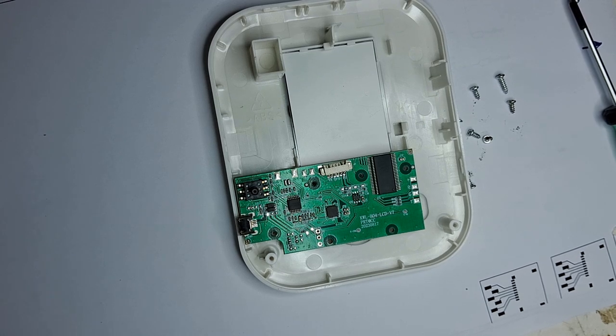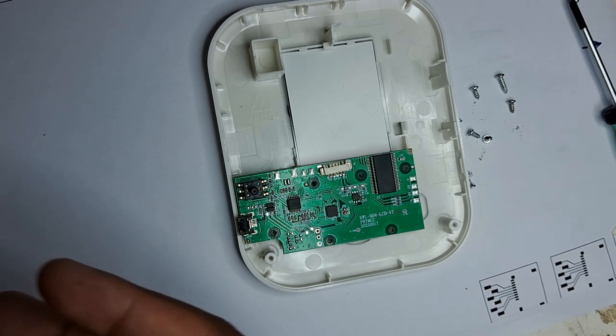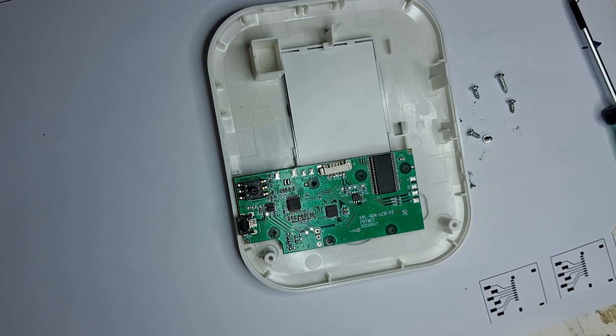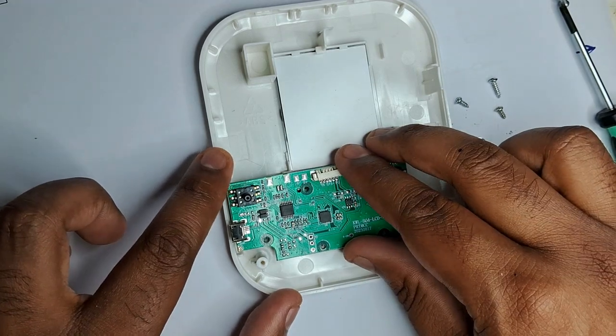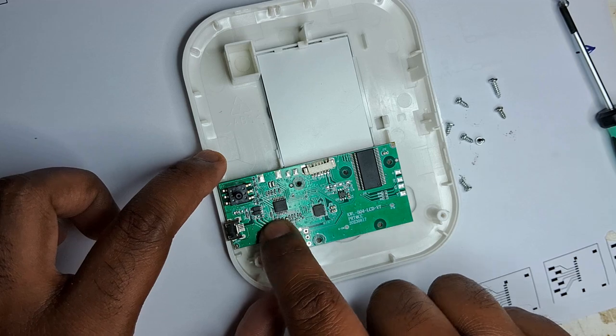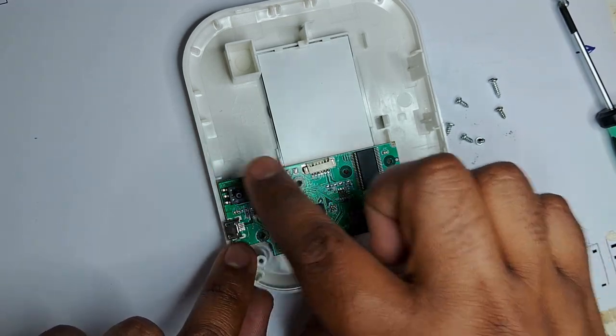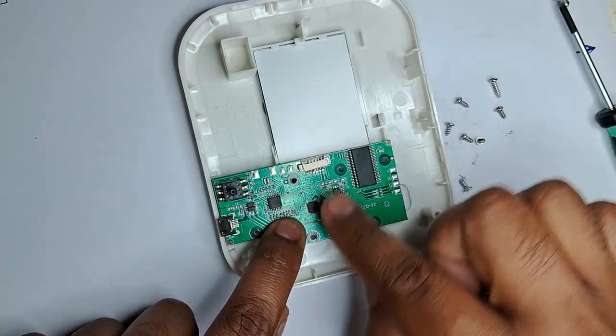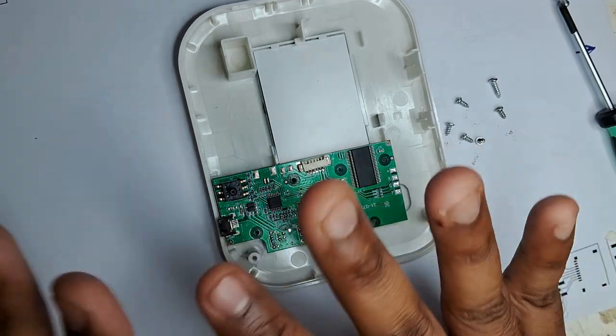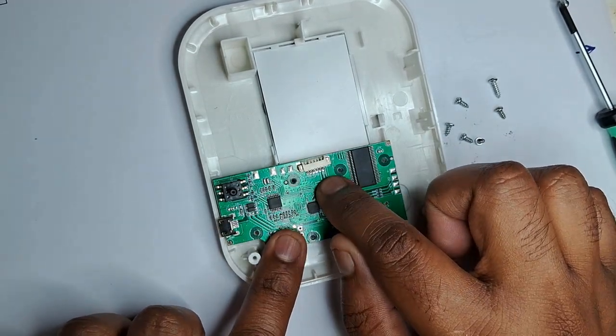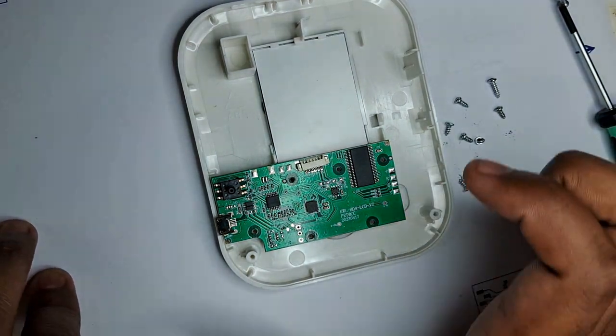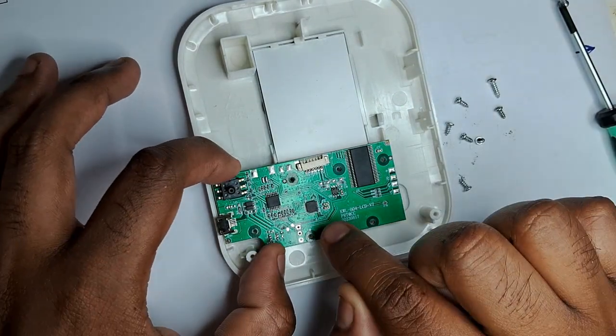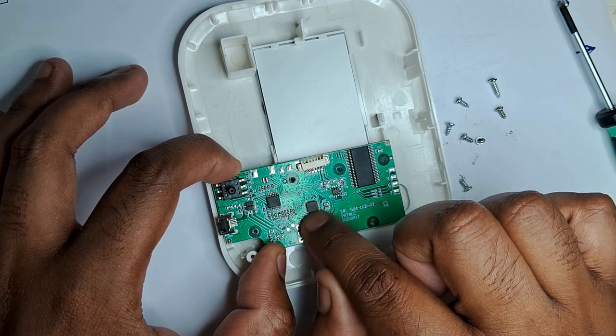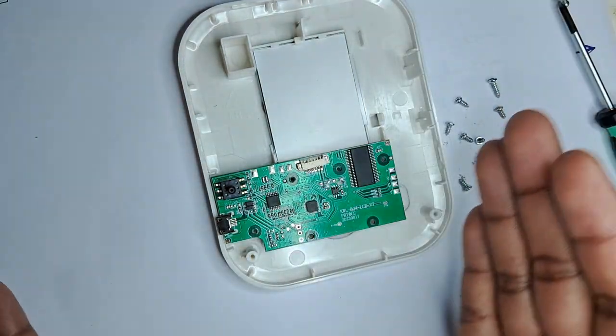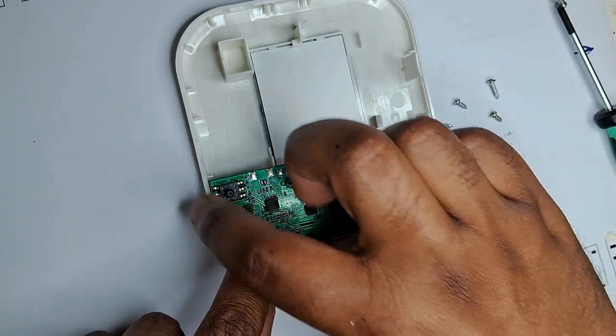Now after discussing the pump, the valve, and how they are interfaced with our main blood pressure cuff, we are going to dive into this circuit, which is the motherboard. It is responsible for interfacing the pressure sensor, the LCD and everything together to calculate the blood pressure using the oscillometric method. In this PCB, this is the main microcontroller. It is the heart of the whole system, and without this, nothing can happen.